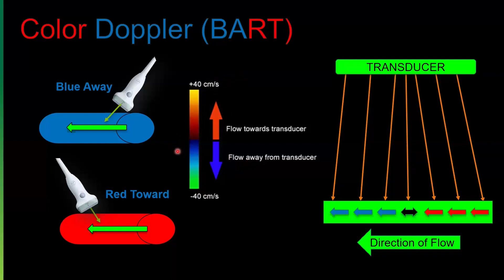So again, looking at this scale with the reds and the kind of yellow, that's flow towards the transducer, and the blues and into the greens is flow away from the transducer. The colors that are on the scale are completely up to you as the operator as well. You can pick straight red and straight blue, although that doesn't really tell you where you might be able to find faster flows. It'll just tell you that this flow is away and this flow is toward.